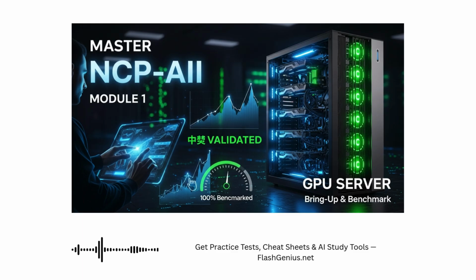You should immediately check the BMC's event logs with the ipmitool sel list, or use NVIDIA Show Health. If an update fails, you stop. You troubleshoot that hardware, and you might have to RMA that component right then and there. You catch a failing DIMM or a bad fan now before it causes a catastrophic failure later.